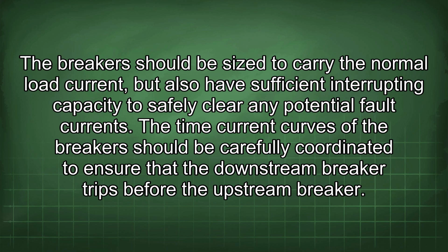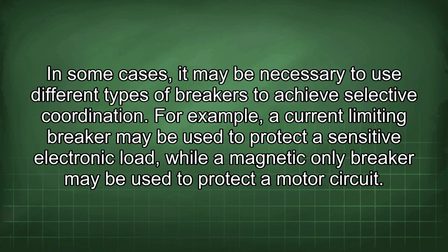The time current curves of the breaker should be carefully coordinated to ensure that the downstream breaker trips before the upstream breaker. In some cases, it may be necessary to use different types of breakers to achieve selective coordination. For example, a current-limiting breaker may be used to protect a sensitive electronic load, while a magnetic-only breaker may be used to protect a motor circuit.